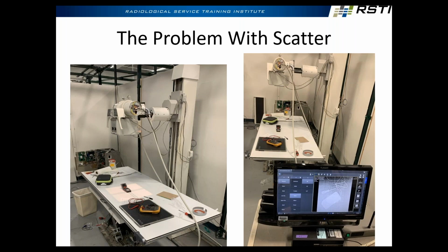And look at the image on the workstation here. What do you see? Keep in mind, this is the actual image being taken. There's enough scatter radiation to not only trigger the AEC into reading, but also show you an image. So it just goes to show scatter is a real thing, right? That was the whole point of this kind of experiment. I expected nothing. I thought it was going to be minimal. There's quite a bit of scatter. The point is time, distance, and shielding. Keep yourself away from the beam, and that demonstrates why, right? See that meter? That meter is in the image of this detector, but it's not part of the actual collimated field of view in that case. Just kind of crazy.